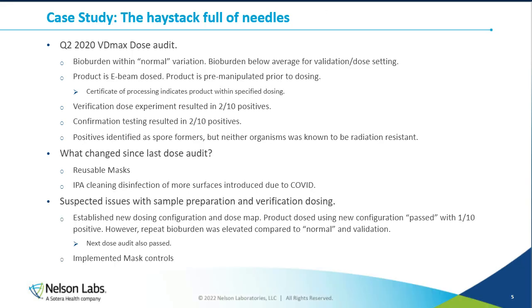So a case study is one where we had a dose audit failure. And normally when we have a dose audit failure for radiation sterilization, we start looking for what changed, what's different from last time. A knee-jerk reaction tends to be, well, nothing changed, nothing's different. However, usually as we start looking through, we start finding various changes and we can look for root causes. However, in this particular example, rather than finding the needle in the haystack, what we instead found was basically a haystack that was full of needles.